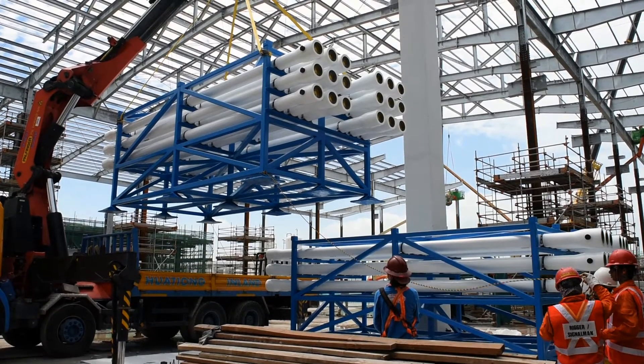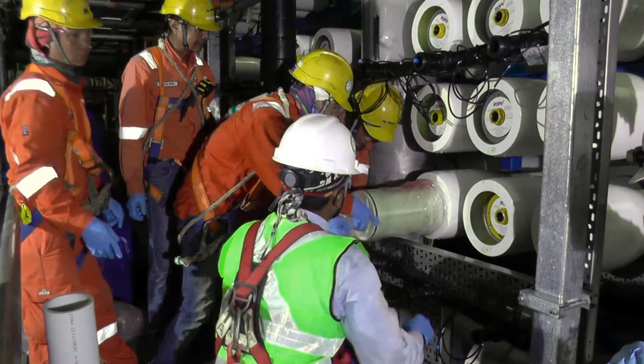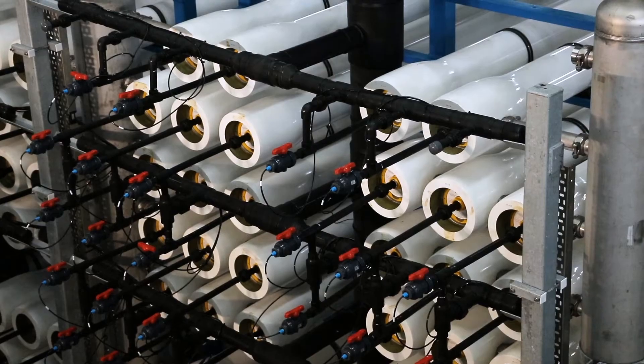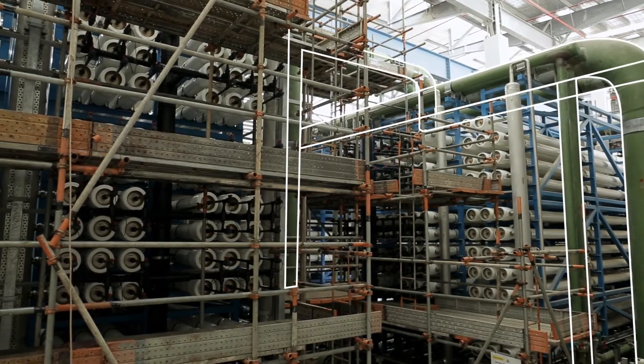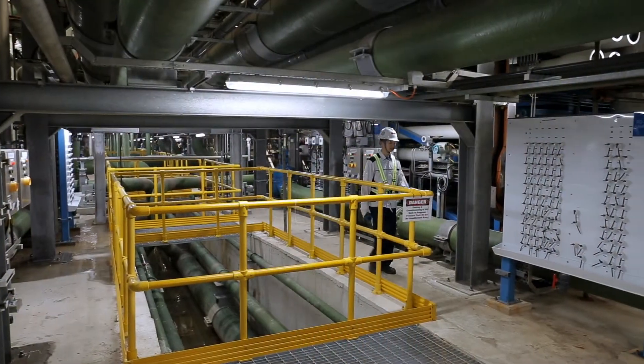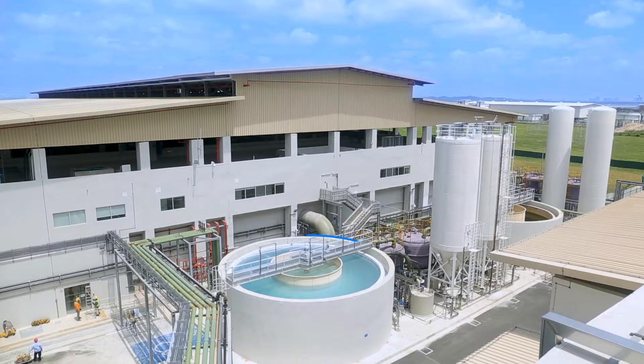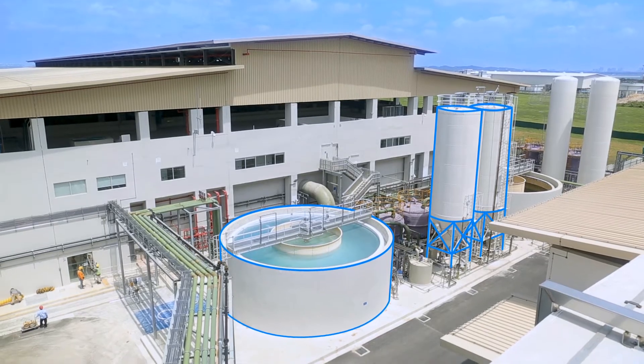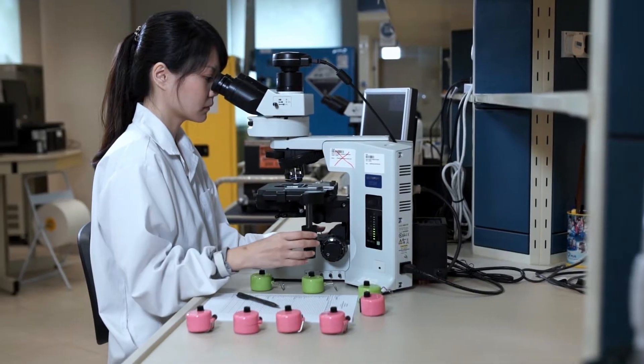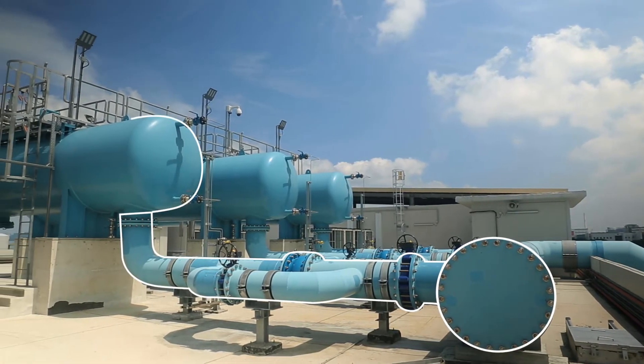Tuas Desalination Plant is equipped with over 14,000 reverse osmosis membranes. The semi-permeable membranes remove salt content of up to 35,000 parts per million. At Tuas Desalination Plant, the pretreated seawater undergoes a two-pass process to ensure a higher quality permeate. The product water from the reverse osmosis process is disinfected with sodium hypochlorite and remineralized with carbon dioxide and lime to meet World Health Organization's guidelines for drinking water quality before it is distributed to homes and industries.